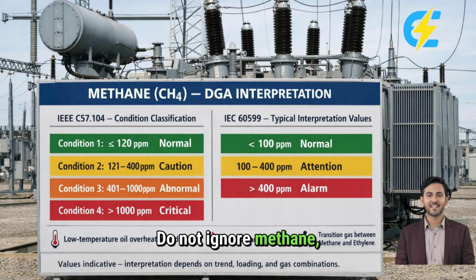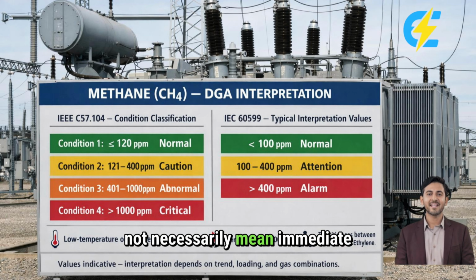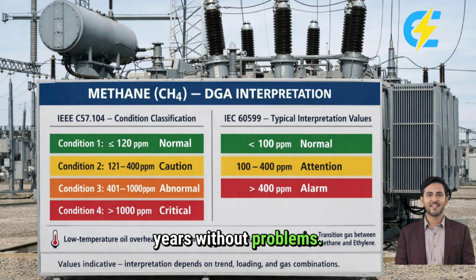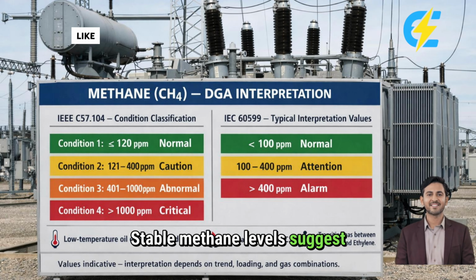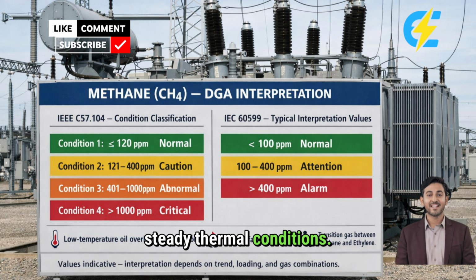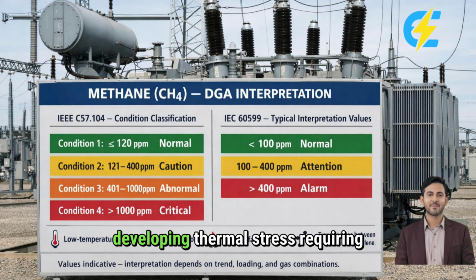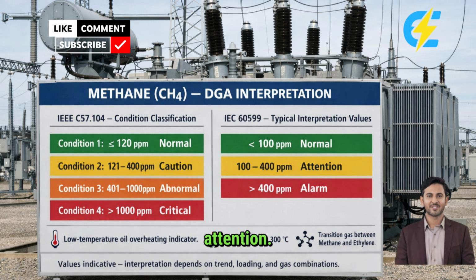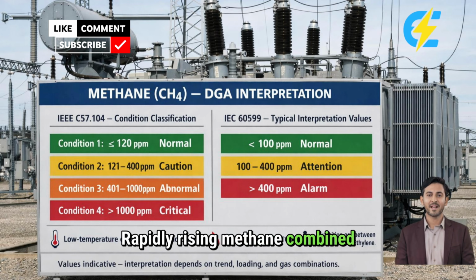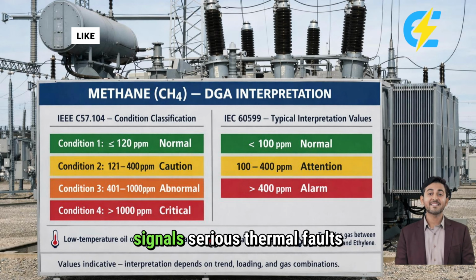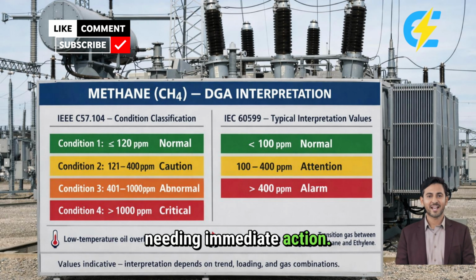Do not ignore methane, but do not panic either. Methane presence indicates thermal activity, but it does not necessarily mean immediate danger. Many transformers operate with detectable methane levels for years without problems. The critical factor is trend analysis. Stable methane levels suggest steady thermal conditions. Increasing methane levels indicate developing thermal stress requiring attention. Rapidly rising methane combined with other thermal gases signals serious thermal faults needing immediate action.